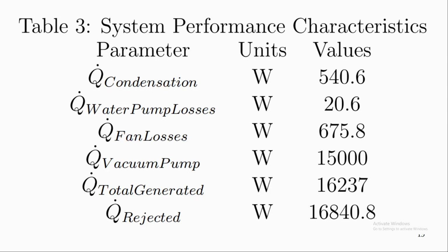And the reason why is because even if I did make a mistake somewhere and the heat rejected was lower than what I think it's going to be here, all that's going to happen is that the temperature of the air in the room is going to increase. And as the temperature of the room increases, the change in temperature between the water and the air also increases. And because of that, the heat exchanger's effectiveness increases as well. And that's not even to take into account the fact that you could have simply increased parameters such as the flow rate of the water, or more importantly, the flow rate of the air. But all of that aside, this is an extremely conservative design.